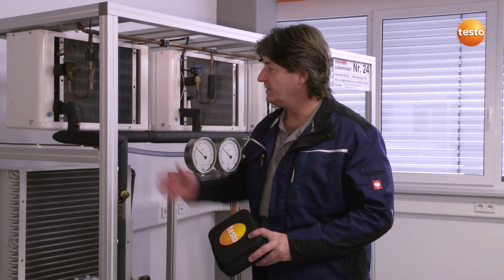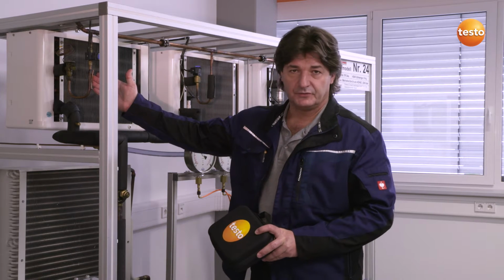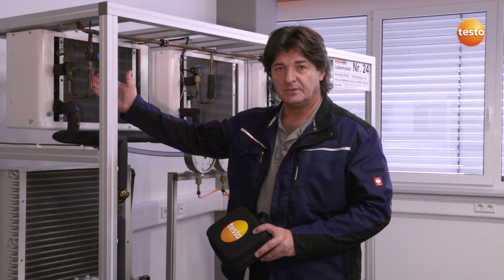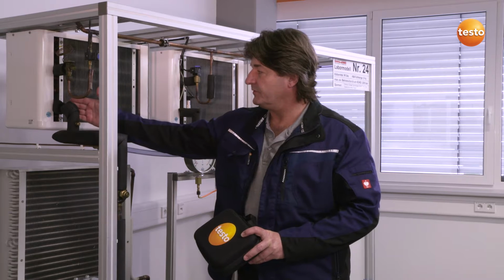The measurement shows me that in this case we have sufficient subcooling of the liquid before the expansion valve, but the evaporator superheating could maybe be improved a bit more. I'm really impressed with how quickly and accurately I've been able to take a measurement, create complete documentation on site, and send it as well.